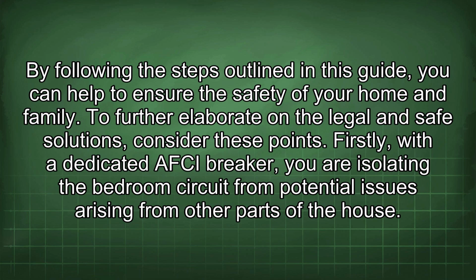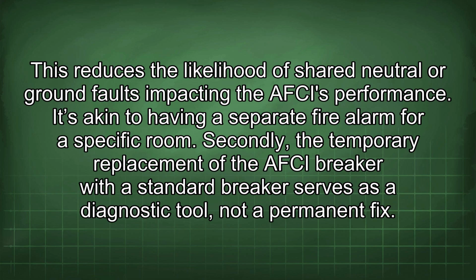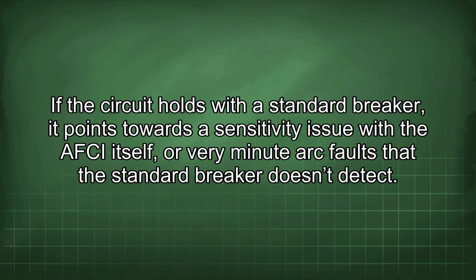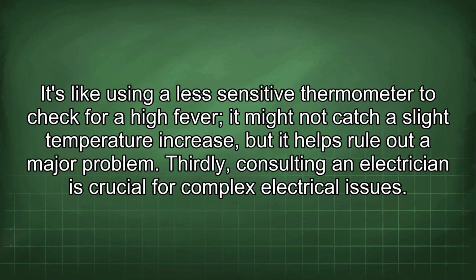Firstly, with a dedicated AFCI breaker, you are isolating the bedroom circuit from potential issues arising from other parts of the house. This reduces the likelihood of shared neutral or ground faults impacting the AFCI's performance. It's akin to having a separate fire alarm for a specific room. Secondly, the temporary replacement of the AFCI breaker with the standard breaker serves as a diagnostic tool, not a permanent fix. If the circuit holds with a standard breaker, it points towards a sensitivity issue with the AFCI itself, or very minute arc faults that the standard breaker doesn't detect. It's like using a less sensitive thermometer to check for high fever. It might not catch a slight temperature increase, but it helps rule out a major problem.